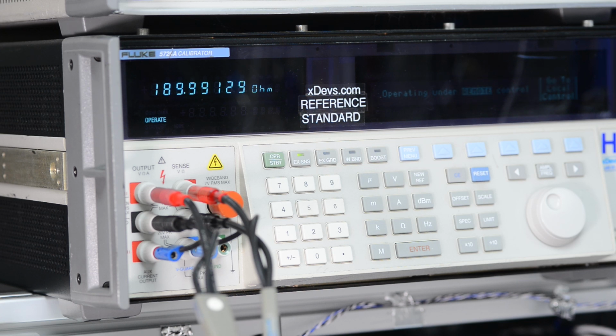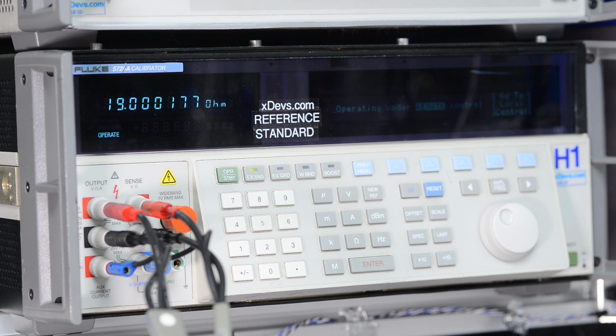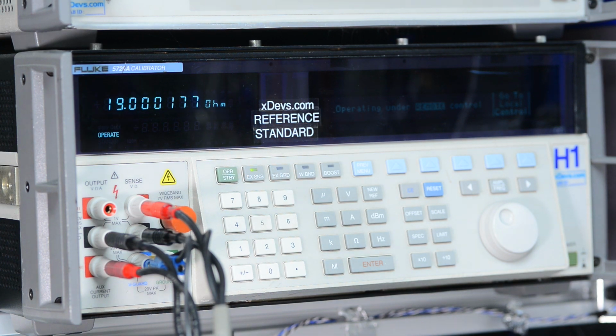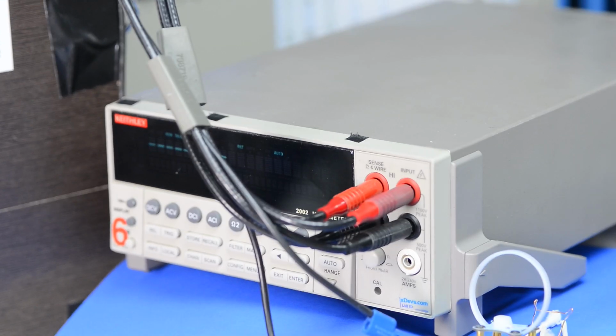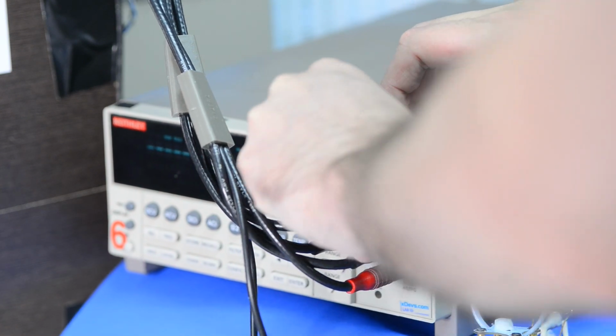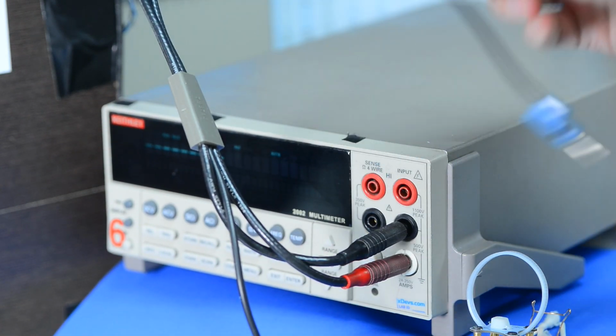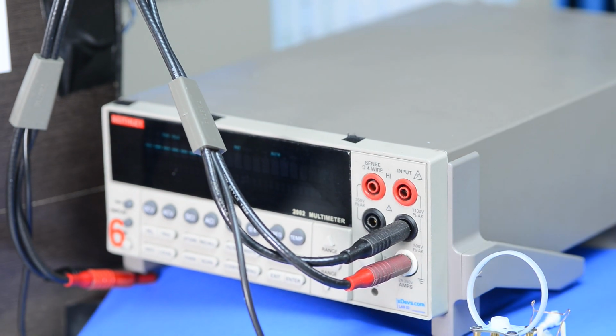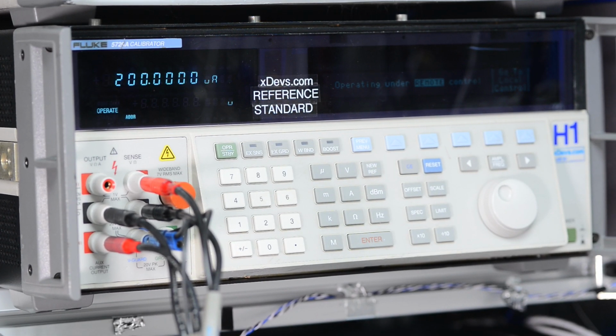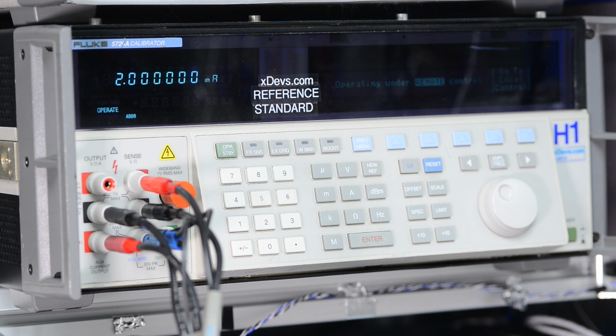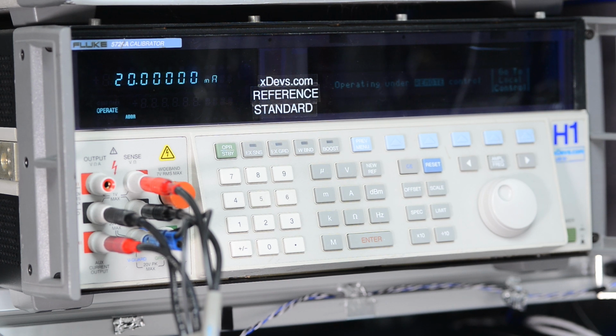And for DC current connection, we need to use white DMM jack for current input. So here at the final 19 ohm point, we can switch the terminals, connect auxiliary current output on the calibrator side, and also switch the terminal on the DMM side to allow current to flow into the DMM. After this is done, we can continue with the test, and first point is 200 microamps, then 2 milliamps, 20 milliamps, and 200 milliamps, and final point is 1 or 2 amps.